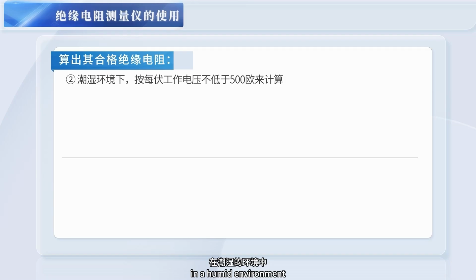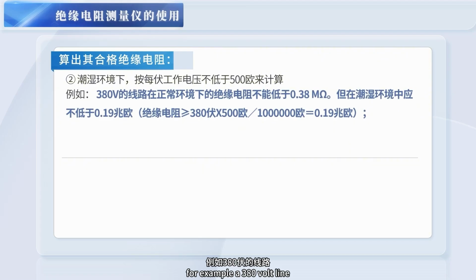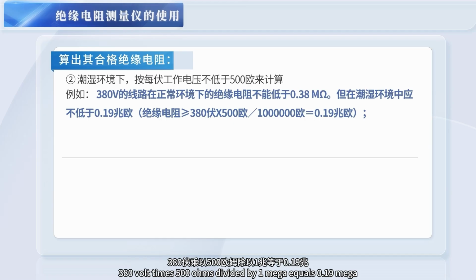In a humid environment, calculate based on not less than 500 ohms per volt. For example, for a 380 volt line, the insulation resistance in a normal environment should not be lower than 0.38 megohms. But in a humid environment, it should not be less than 0.19 megohms. The insulation resistance is greater than or equal to 380 volts times 500 ohms divided by 1 megohm, which equals 0.19 megohms.